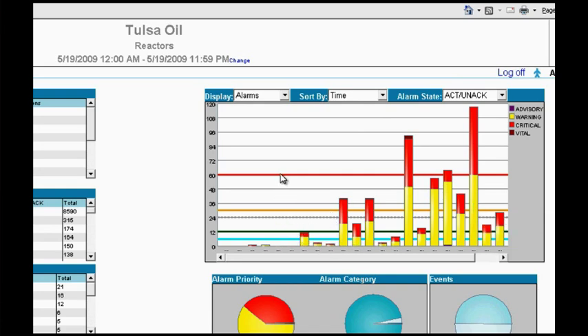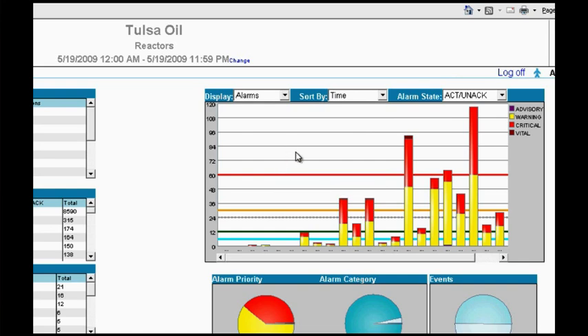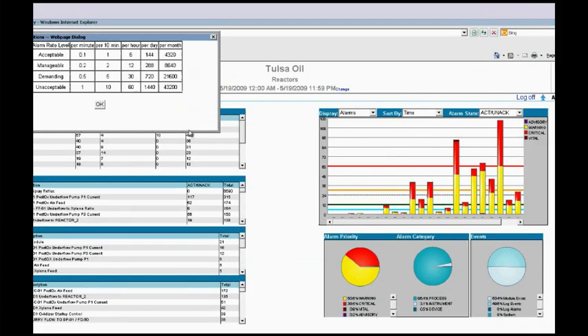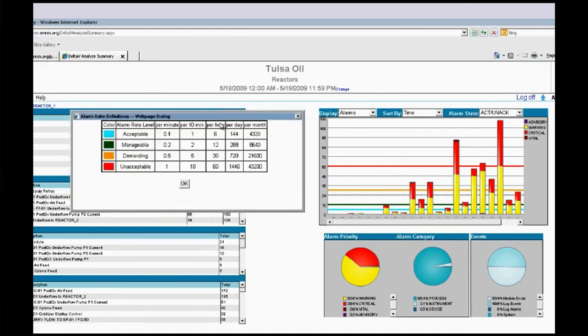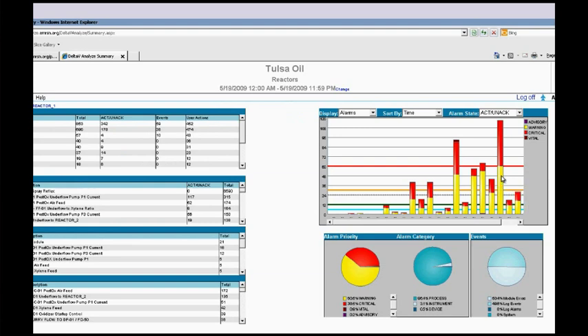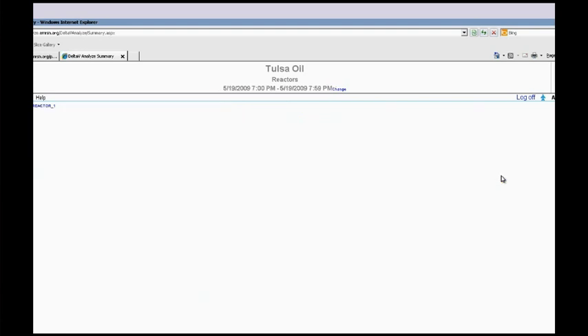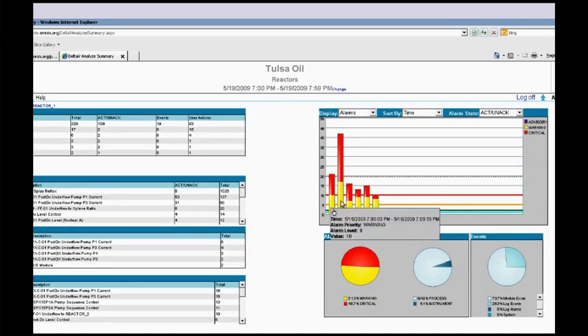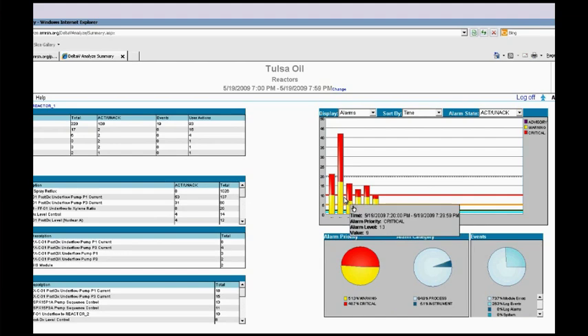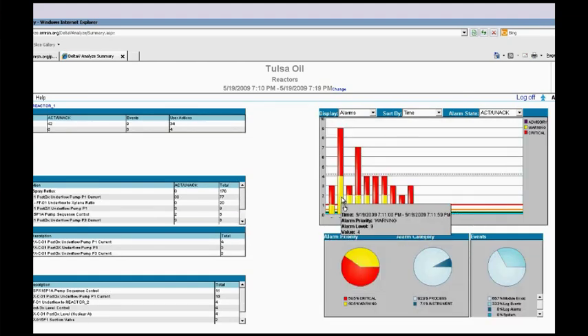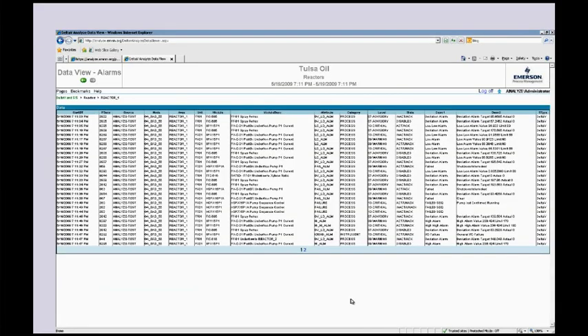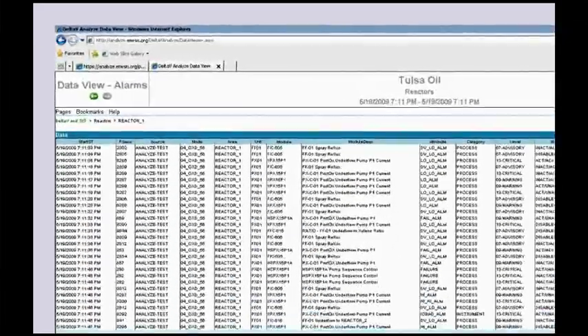You may have also noticed these bars across the screen. These are actually those alarm rates. To refresh your memory on those, let's just take a quick look. Here they are. These are the defaults that are per industry standards. You may have changed these to correspond to your alarm philosophy. And again, just continuing with drilling in, we can take that 7 p.m. hour where the highest alarms occurred. And we can look at things in 10-minute increments. We can look at things in 1-minute increments and continue to drill on in. So that's the power of Delta V Analyze to drill, both by scope and also by time.